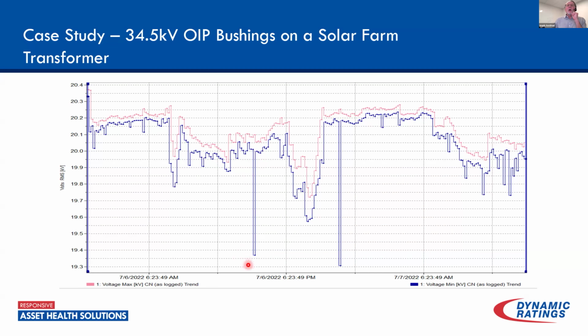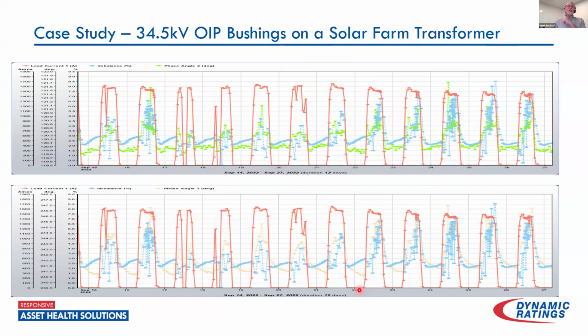You're seeing fairly large deviations in voltage, very short-term as well. But one thing that's very interesting when we look at the data on the unit is that there seems to be almost two different conditions here. Here's where we're generating. Not surprisingly, we see a lot of changes in phase angle and high spikes in imbalance current. But when we're offline, things are a little more stable.